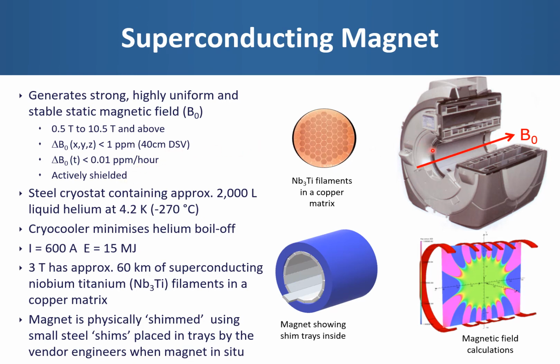If we look inside the magnet here, we can see the magnet windings, which are along here, sitting inside the bath of liquid helium. The number of turns and spacing of those solenoidal windings are very carefully calculated by the magnet designers in order to produce the most uniform static magnetic field in the center of the magnet. There are several internal radiation shields that are mechanically cooled by the cryocooler, as well as layers of vacuum. And outermost here we have the active shielding coils, also superconducting, sitting in a bath of liquid helium.